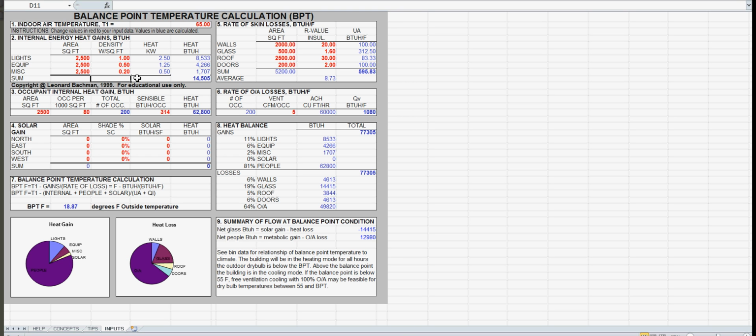based on a building of 2,500 square feet, if we also had 2,500 square feet of occupied area, and they might not be the same area, but let's assume they are for now, we would find the occupant density by code, in this case 80 occupants per 1,000 square feet, which tells us that there are 200 occupants in the building.